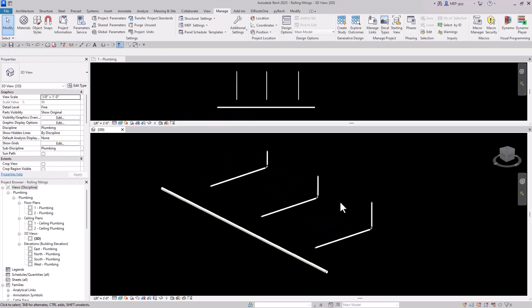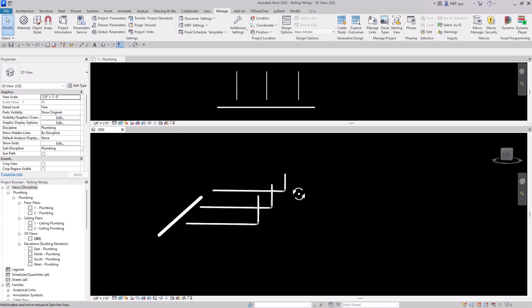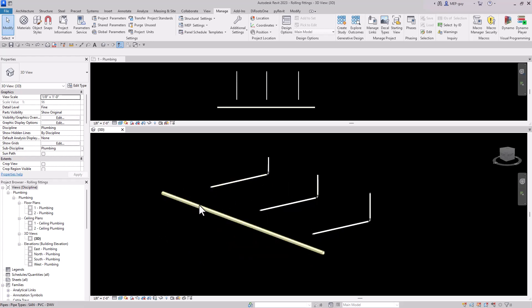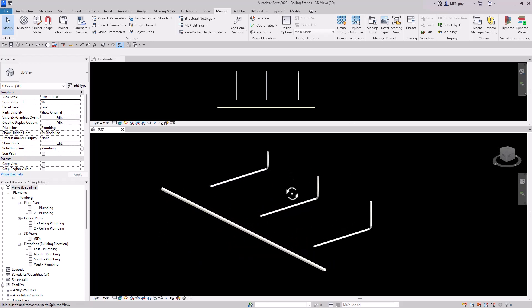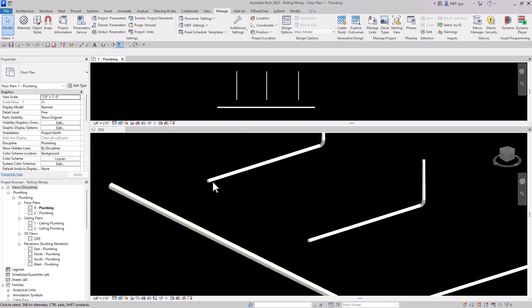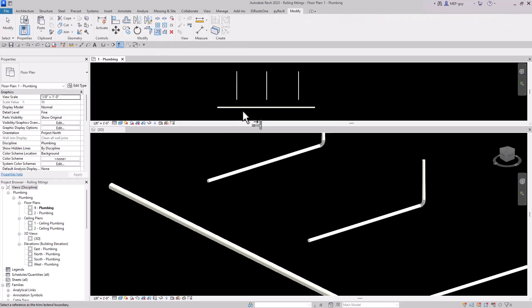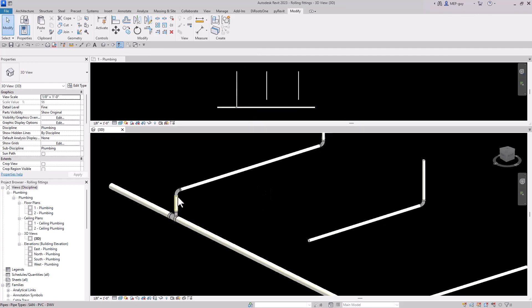For the next example, we have three branch pipes going into a sanitary main that's very low below the ground. These branches are at different elevations and we want to roll this piping into the main. The first way: go to a floor plan and use the Trim/Extend command — specifically Trim Extend Single Element. Click the main, then click the branch piping, and Revit will draw a 45 degree angle.